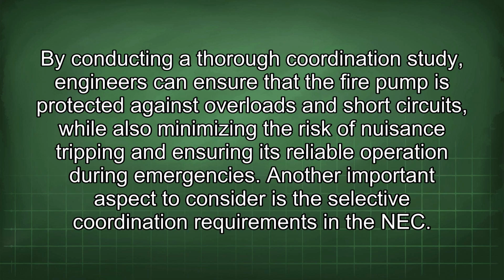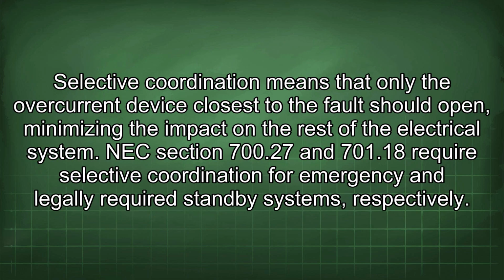By conducting a thorough coordination study, engineers can ensure that the fire pump is protected against overloads and short circuits, while also minimizing the risk of nuisance tripping and ensuring its reliable operation during emergencies. Another important aspect to consider is the selective coordination requirements in the NEC. Selective coordination means that only the overcurrent device closest to the fault should open, minimizing the impact on the rest of the electrical system. NEC Section 700.27 and 701.18 require selective coordination for emergency and legally required standby systems, respectively.